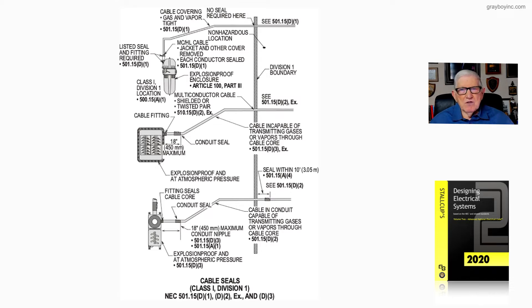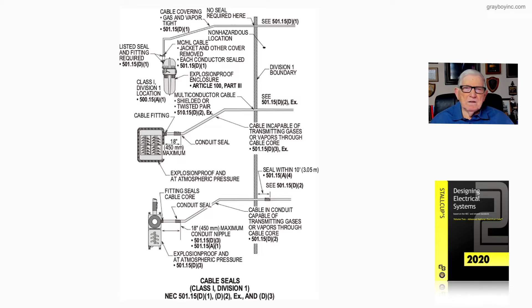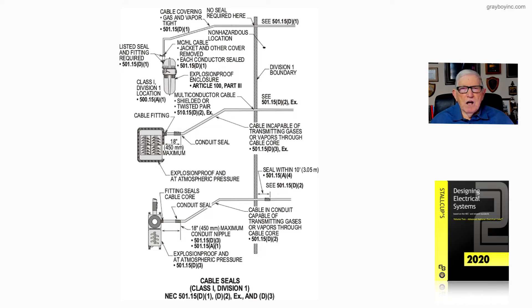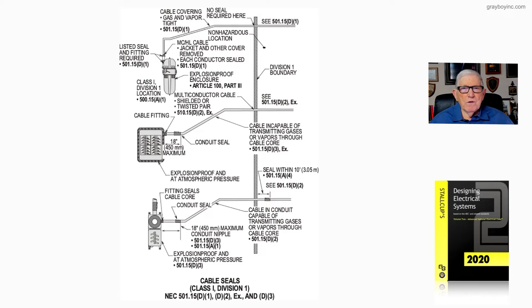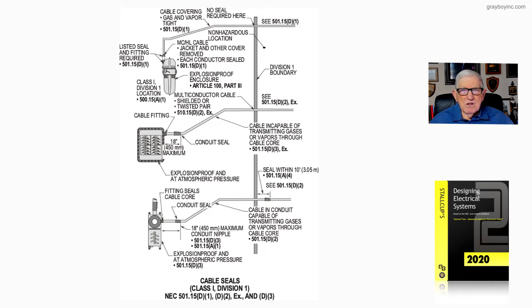We just come in, have a seal around the core, and this is where we use the fitting, a boot that will seal the core, or we use a compound like the top illustration. We use a listed seal and fitting that would seal around the core and the fitting would seal the conductors inside. That's the difference between the top one and the second one.